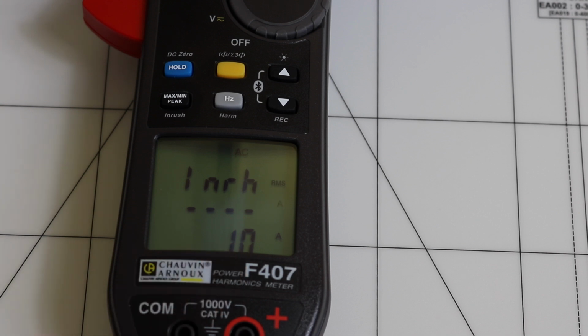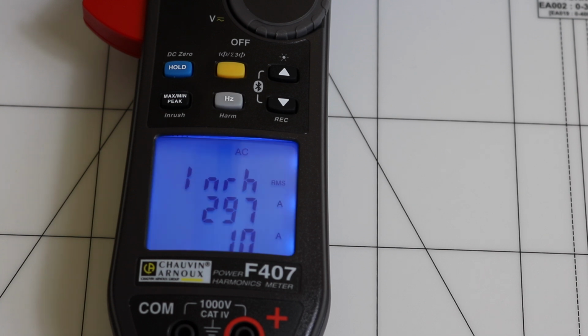That's the lowest it can actually be, which is your 10% of your 100 amp range that you see there. So we have our little program set up on our injection test set. This gives me a current for 100 milliseconds and it should be 300 amps inrush measurement. So we'll give that a little run. And you see we've picked up 297 amps this time. So that's the basic functionality there.